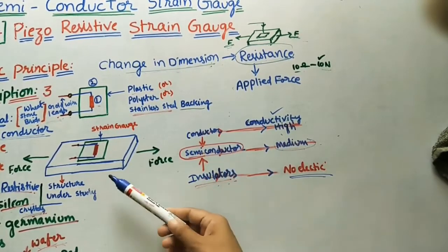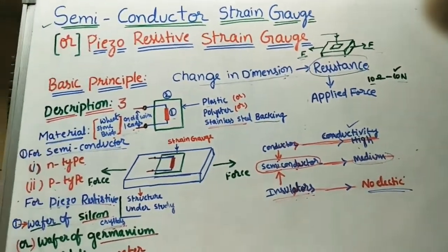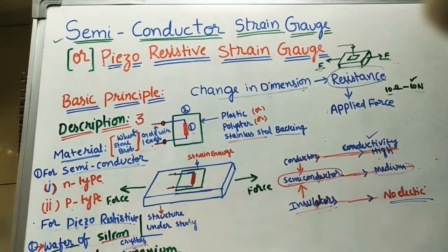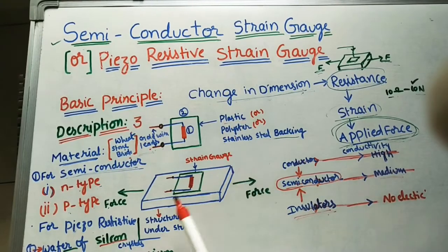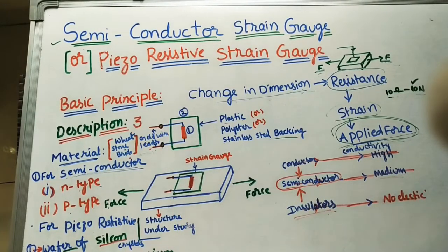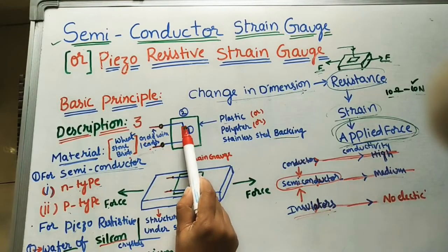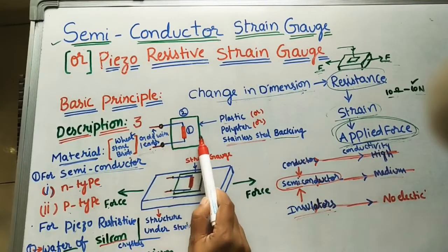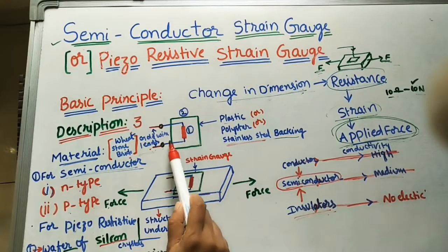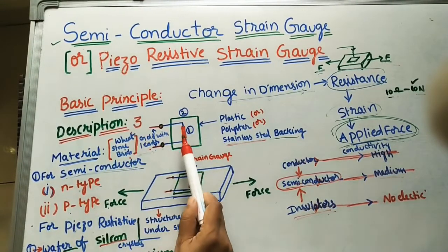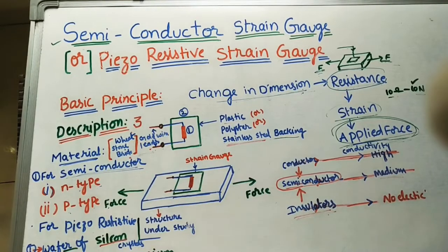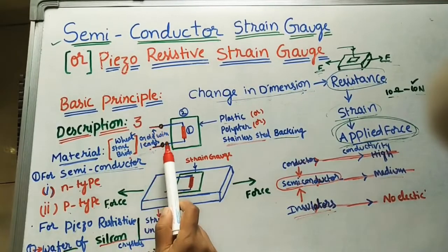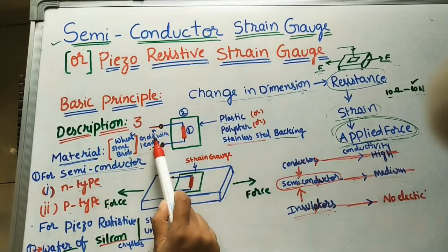This semiconductor material is used as the first part and is fixed in the strain gauge. The second part is the backing plate — it may be plastic, polyester, or stainless steel. We paste the semiconductor material onto this backing plate. The third part is the gold leads: we take the semiconductor wires and fix them with gold wires by soldering at two ends. These leads connect to the Wheatstone bridge, which is the third part and measures the change in resistance in the semiconductor material.